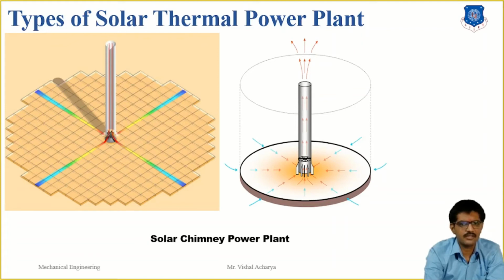The air speed before and after the turbine is about the same. The output is proportional to the product of the volume flow per time unit and the pressure difference over the turbine. With a view to maximum energy yield, the aim of the turbine control system is to maximize this product under all operating conditions.